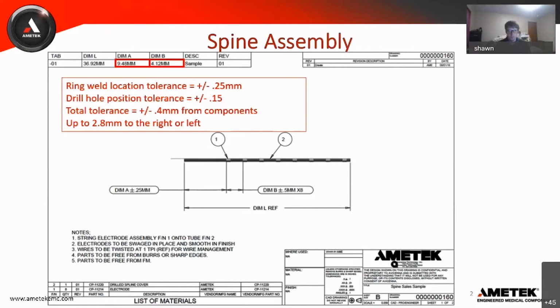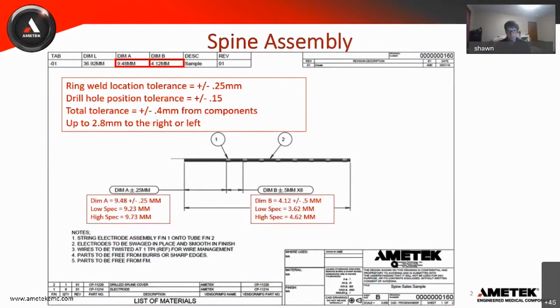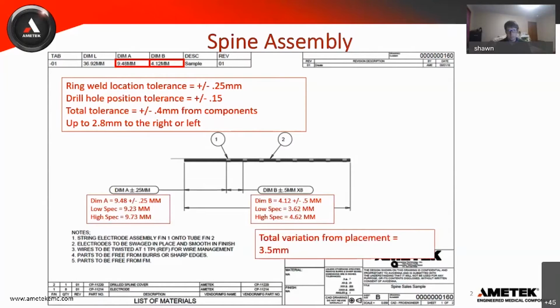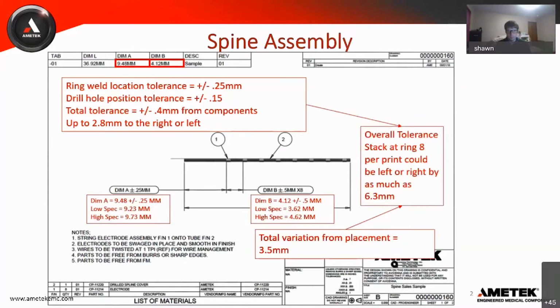Now we look at the electrode location tolerance stack. Here we have plus or minus 0.5 millimeters of tolerance, again multiplied by 7 to get 3.5 millimeters variation. We add up all of this variation and we get a total of plus or minus 6.3 millimeters. Variation adds up, and therefore design for manufacturability is key. This is all important because to get the electrode locations within specification, we need to implement controls within this process.